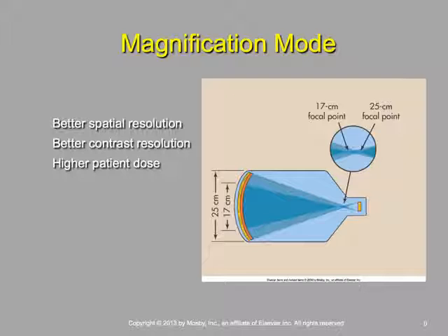So this is helpful for us because at times when we're using the fluoro machine, we might want to get a bigger picture, right? And they probably magnify things in a limited degree in fluoro. Well, why don't they do it more often? Because it would be helpful to have things magnified, right? You'll notice that anytime we use the magnification, what we're shifting is this focal spot inside of the tube. We're just shifting that focal spot back or forth, right?